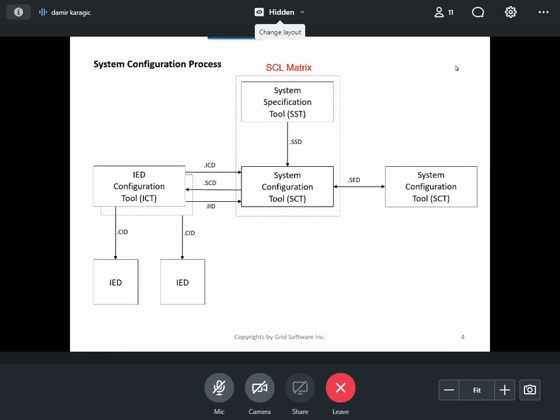Part 61850-6 of the standard specifies engineering software to be used in this process. The first is the IED configuration tool. That's a tool of the relays. The relays have software that is capable of producing an ICD file. These are template files. This is not configured, just template files that show capabilities of IEDs. That's the extension, IED capability description.